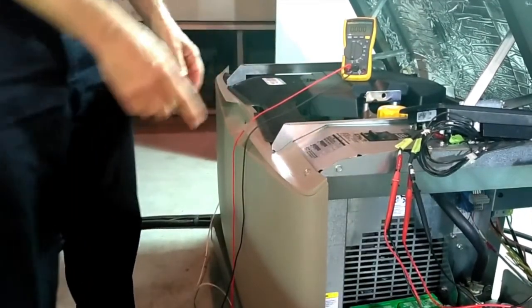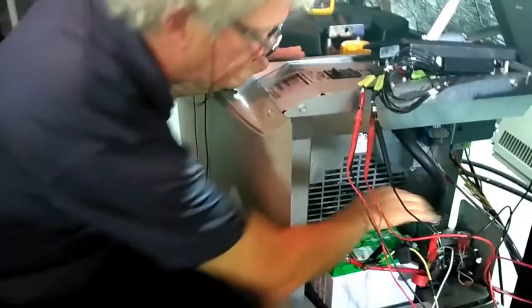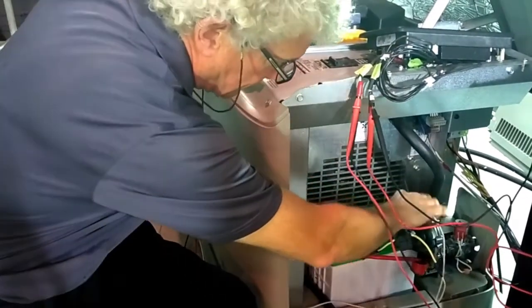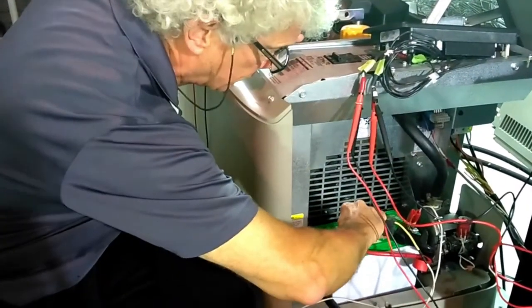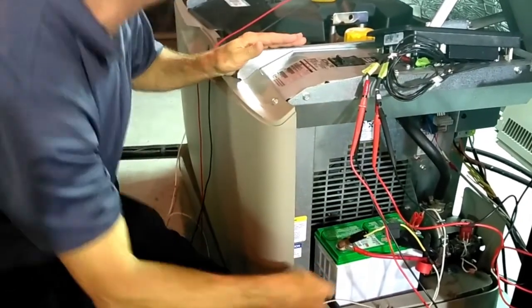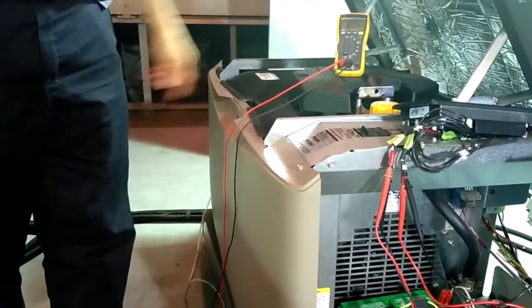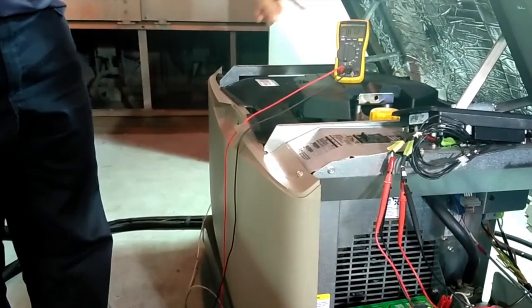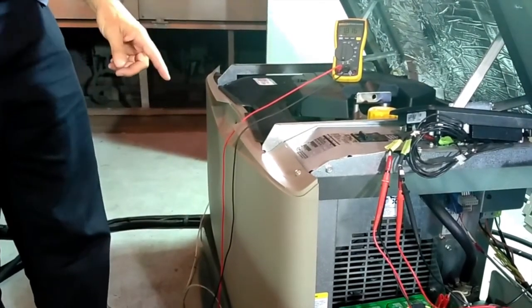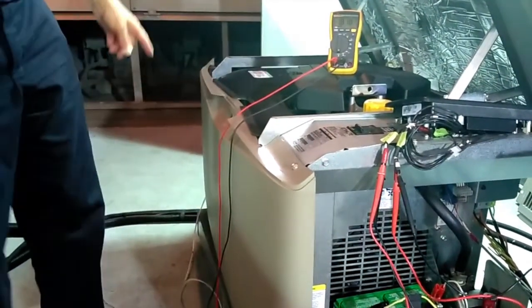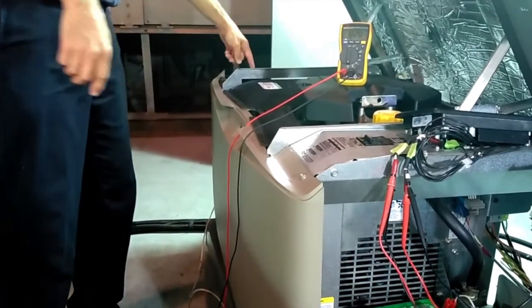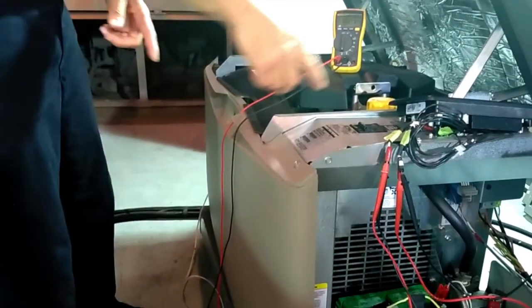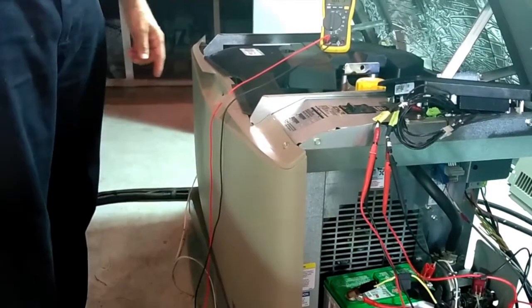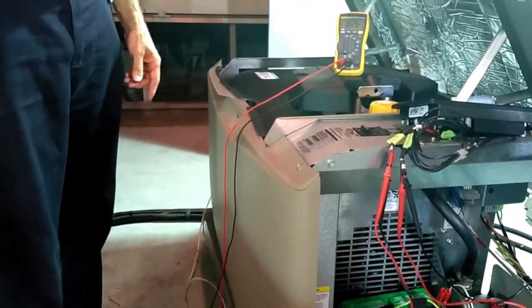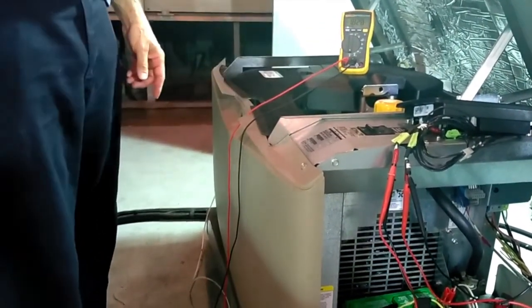So now what I'm going to do is I'm going to take my battery leads, I'm going to hook up my positive, then I'll hook up my negative. You see a little arc there, and here I'm reading 1.7 amps now, or 1.8 amps. So that's my complete circuit. So the voltage is going in through the meter, down through the rotor, and back to the battery. So I have 1.8 amps of flow through the rotor right now with a 12-volt battery.